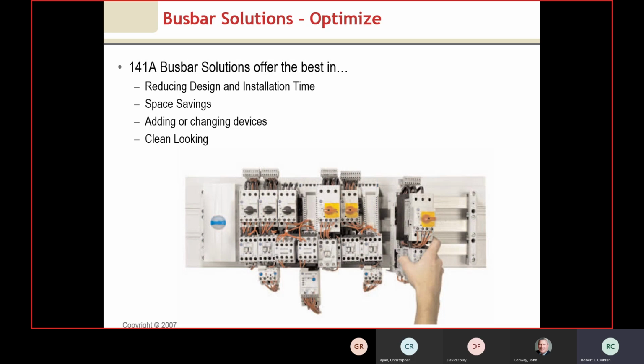I have a customer I worked with years ago who builds a lot of panels and uses a lot of starters. We sat down together and showed an $80,000 a year savings from using this system, just from the wiring time, assembly of units, mounting, and so on. So if you've got a number of starters in the unit—and by the way, you can connect drives to this and other things—this might be an option.